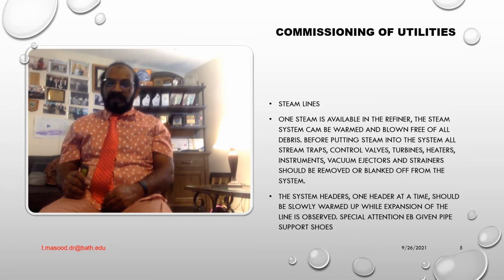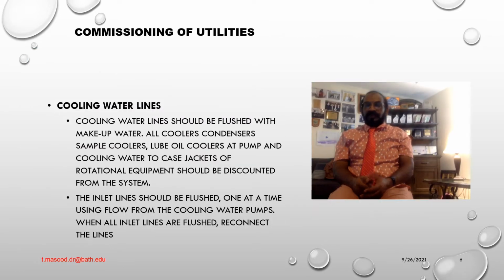Usually a lead or aluminum impingement plate is installed at the opening where the steam is being vented. When the number and size of the indents are within acceptable limits, the line is cleaned. Cooling water. Cooling water lines should be flushed with makeup water. All coolers, condensers, sample coolers, or lube oil coolers at pumps and cooling water to case jackets of rotating equipment should be disconnected from the system. The inlet lines should be flushed.